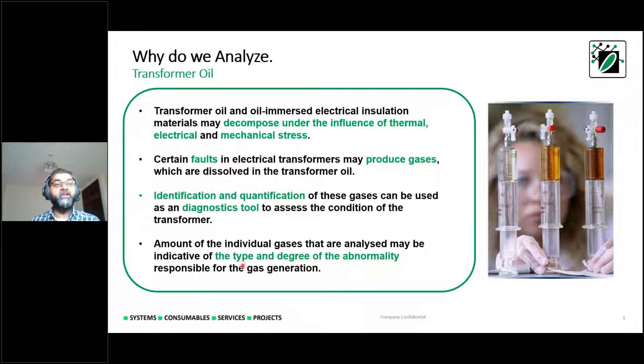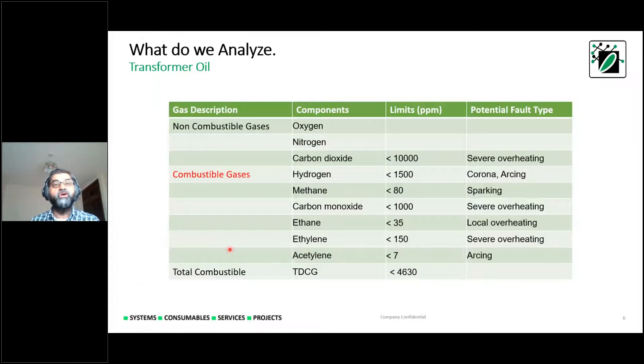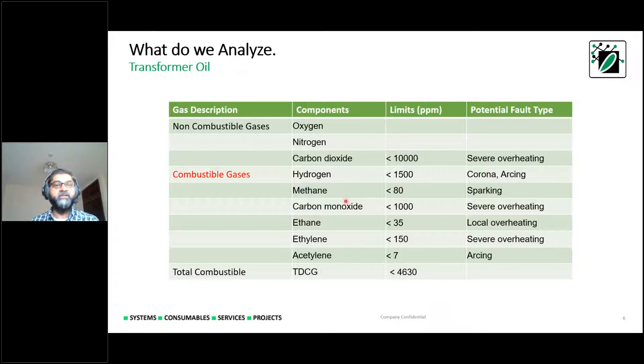The amount of individual gases analyzed can indicate the type and degree of abnormality responsible for gas generation. For example, if methane is increasing beyond 80 ppm, there may be a sparking condition; if acetylene exceeds 7 to 10 ppm, it indicates arcing. There are also total combustible gas limits — around 4630 — alongside non-combustible gases. All these need to be monitored regularly to prevent transformer breakdown.